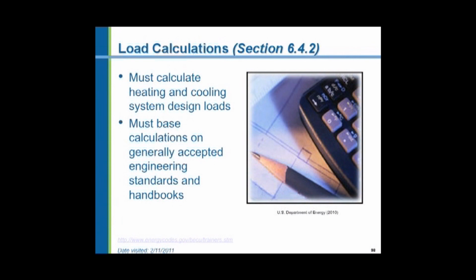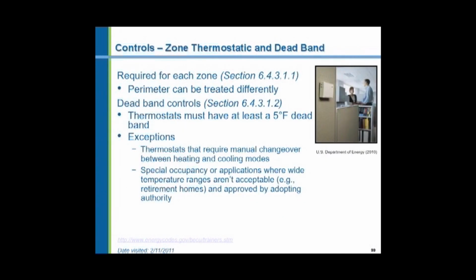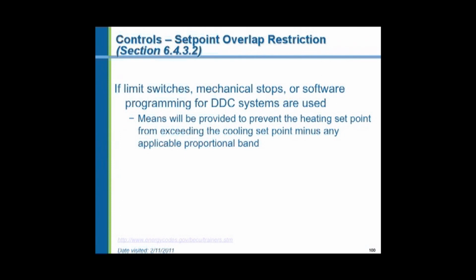Now again, the engineer must demonstrate the sizing of his equipment. He has to submit the printout sheets from his heating and cooling load calculation programs. The thermostats in the units and the control zones have to have deadband controls. What that means is that for a 5-degree range around the standard temperatures for human comfort, between 70 and 75 degrees, the system does nothing. It does neither heating nor cooling. Everything is off. That's called a deadband. Now there are some exceptions to that, special occupancies, maybe retirement homes, but you have to clear this with the local code officials before you apply any systems like that. You cannot have any overlap between heating and cooling.